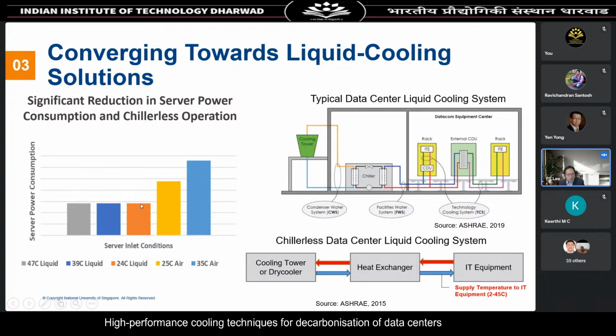So what is the implication? The implication is that for liquid cooling, you can actually operate without any chiller. The conventional way of performing liquid cooling is shown in the top right figure, which requires coupling it with a chiller system, as shown here. So the supply or server inlet temperature will obviously be low, for example at 24 degrees Celsius. But the downside is you need a chiller system, which takes up space and consumes additional energy.